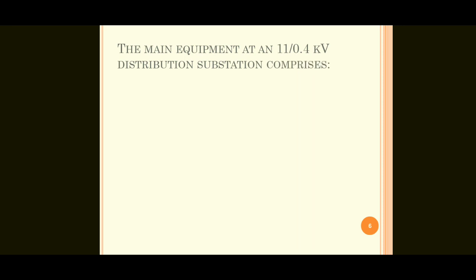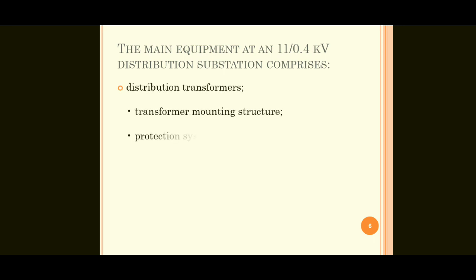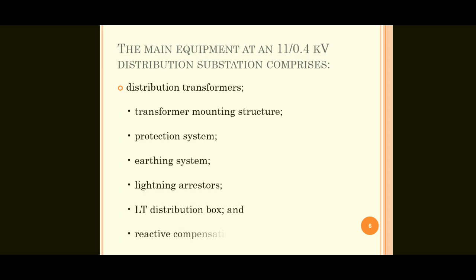Next one, the main equipment at an 11 kV by 400 volt distribution substation comprises distribution transformers, transformer mounting structure, protection system, earthing system, lightning arresters, LT distribution box, and reactive compensation. These are the main equipment in 11 kV by 400 plinth mounted transformer or distribution substation.